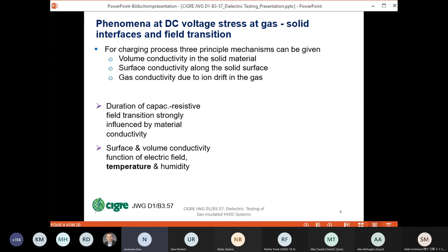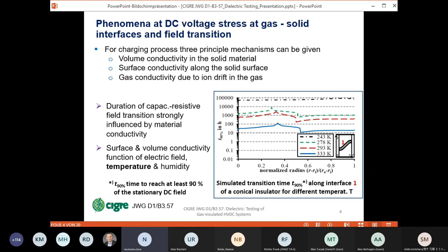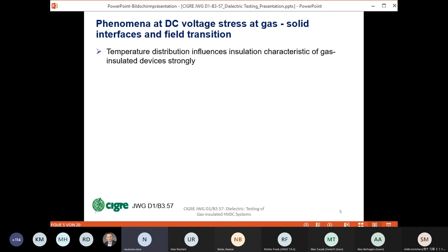Here you can see the transition time T90, that is the transition to 90% of the DC steady-state status. And you can see there is a strong dependence on the temperature, but there is not only a dependence on the temperature, but also on the temperature distribution, that also influences the insulation characteristic of the gas-insulated devices strongly. As you can see here, there is the development of the DC field at different locations of the insulator, depending on the ambient temperature. And you can see the ambient temperature at 40 degrees Celsius is much faster than at 20 degrees Celsius.